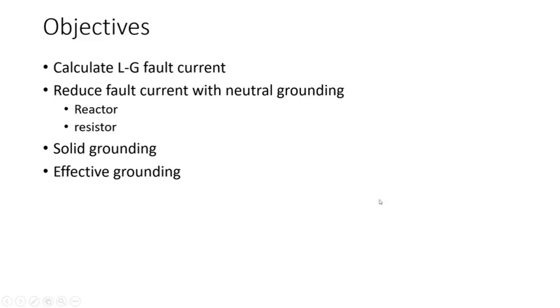The objectives of this video series: we'll learn how to calculate the line-to-ground fault current, reduce the fault current with neutral grounding — starting with a reactor, then a resistor, then solid grounding. We'll verify each case because each time you add a reactor or resistor you're adding impedance, and you may not maintain effective grounding of the system, which is very important.